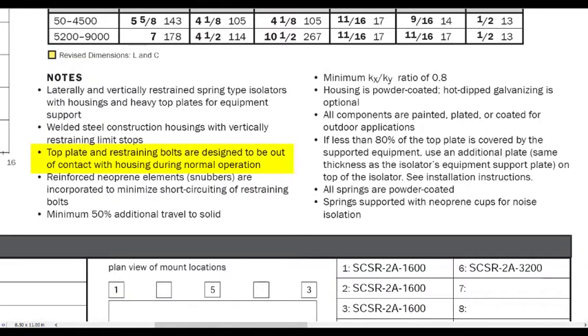This note says top plate and restraining bolts are designed to be out of contact with housing during normal operation. So combined with the working clearance shown in the graphic above, we'll want to make sure those components are not in contact. Here it says reinforced neoprene elements, snubbers, are incorporated to minimize short-circuiting of restraining bolts. We'll want to take a look at those and see that they're doing their job.